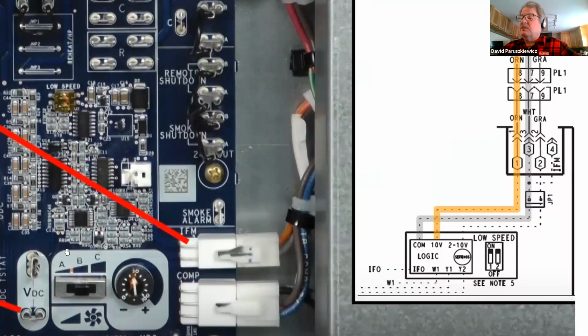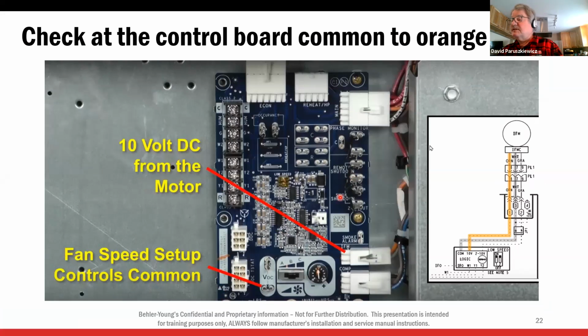That 10 volts went through these switches here. We set it to 9. And when that blower gets a call, it's going to send the 9 volts back down this pin, down this gray wire, back to the motor to tell the motor to run. All right. So again, we adjusted it and it's going to take that voltage and send it back to the motor, and that tells the motor what speed it's going to be. So I can actually check for that voltage right there.